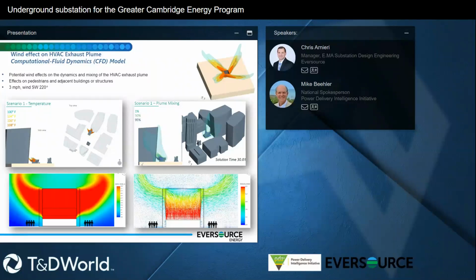The exhaust side was particularly an issue, because anything with air particulates—yes we have air filters—but everything leaving, especially the heat, since air filters don't block heat, we had to do a full computational fluid dynamics model of this area. In the upper right, you see the 3D computational model showing the exhaust stack blowing out the louvers of the exhaust tower, and it's a pretty violent plume coming out.